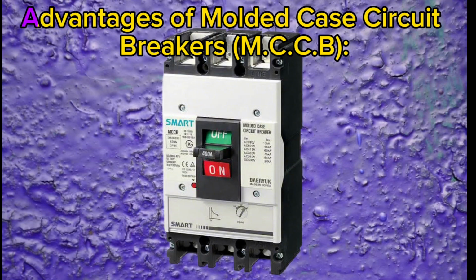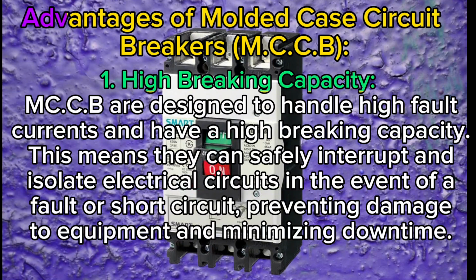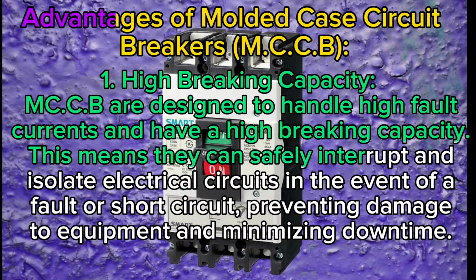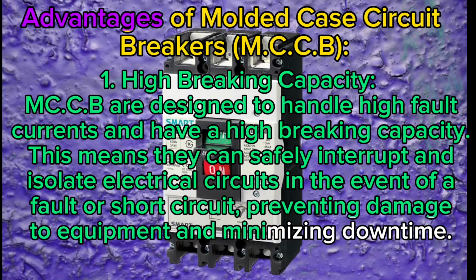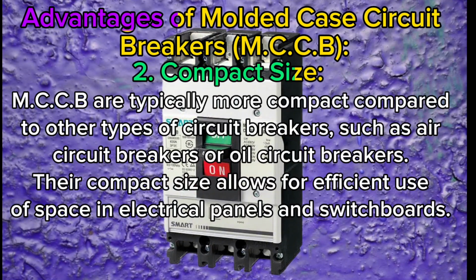Advantages of molded case circuit breakers, MCCB. 1. High breaking capacity. MCCBs are designed to handle high fault currents and have a high breaking capacity. This means they can safely interrupt and isolate electrical circuits in the event of a fault or short circuit, preventing damage to equipment and minimizing downtime. 2. Compact size.